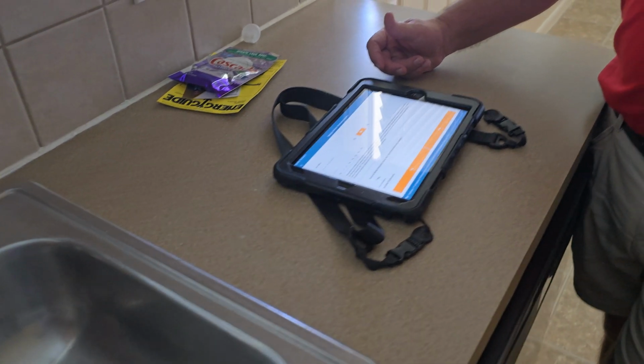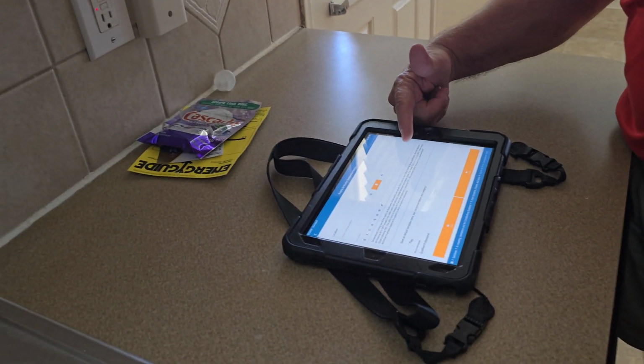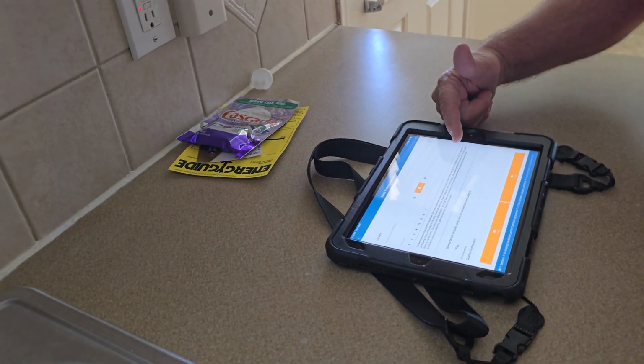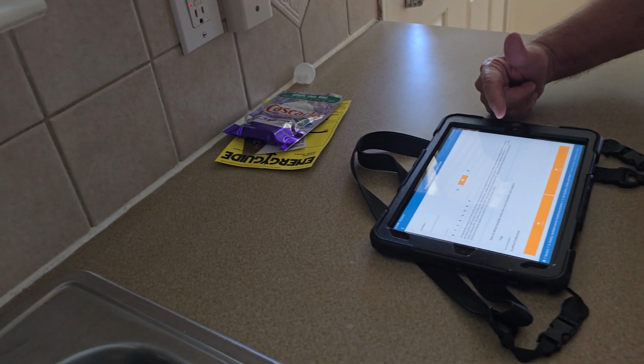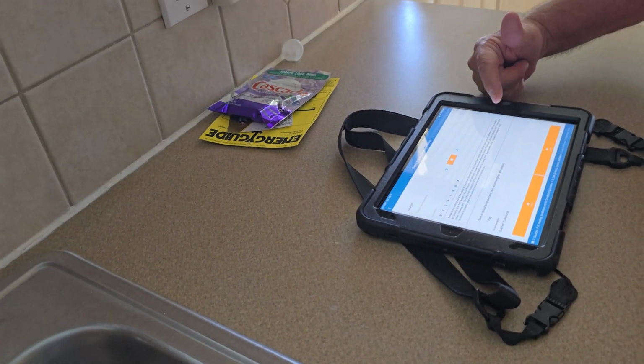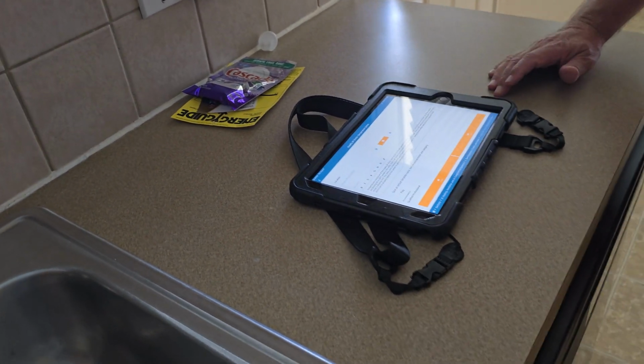So the minimum I should see is 56 at the register. Okay, so the master bathroom is blowing 64 degrees. The master closet is 74 degrees. The utility room is 65 degrees. And the half bathroom is 61 degrees. It's like it's not balanced.